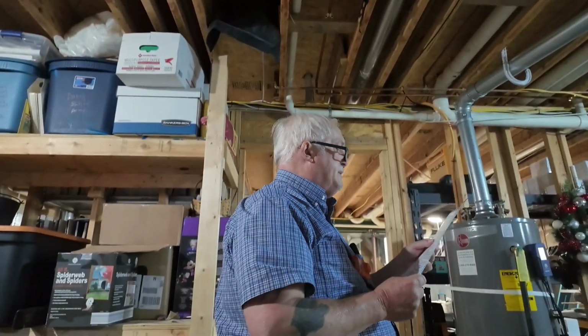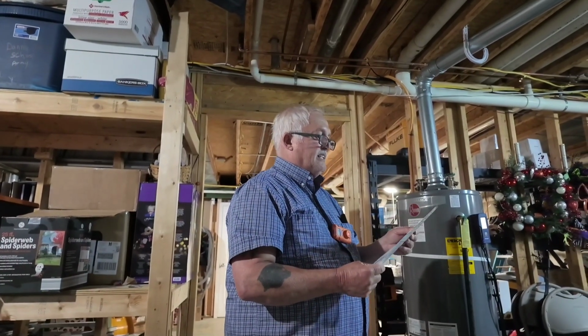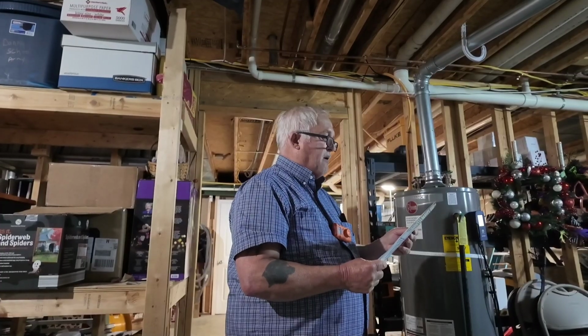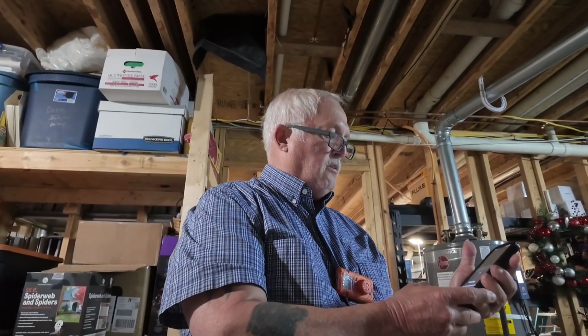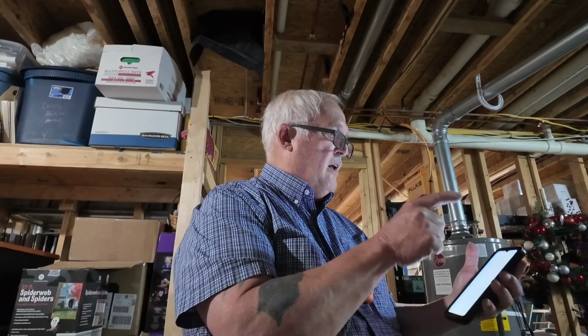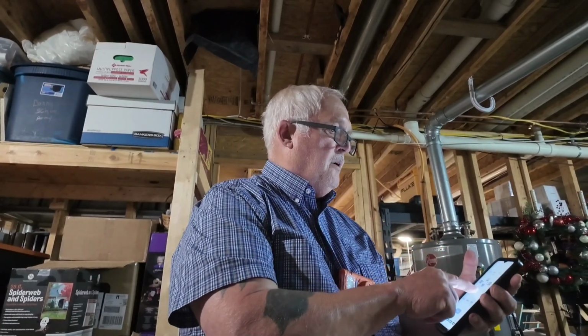And it says assess spillage. Warm vent pertains to an appliance for which the heat setting is turned to on. Assess spillage at 2 minutes of main burner operation. So I'm going to set my timer. You can ask me as the proctor to set the timer. I will do so. I'm going to set it for 2 minutes. I'm going to take a mirror.